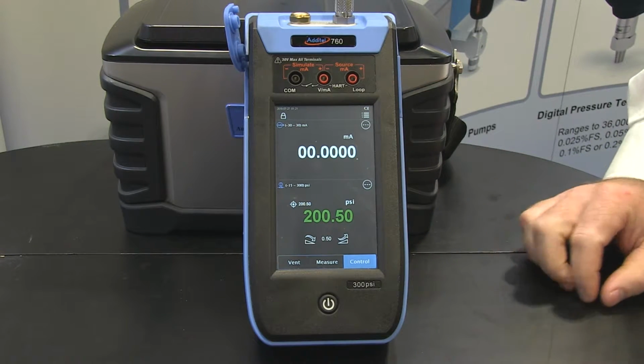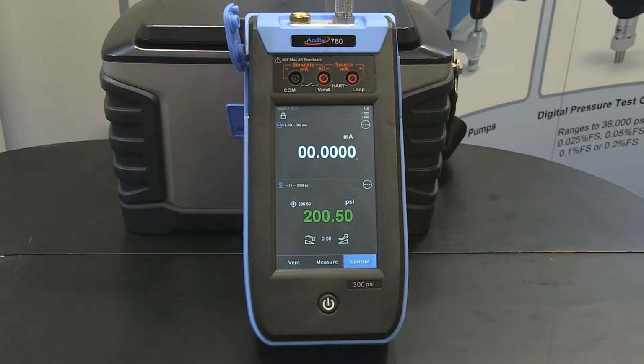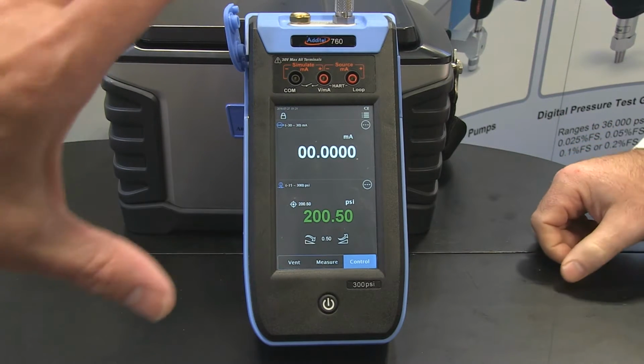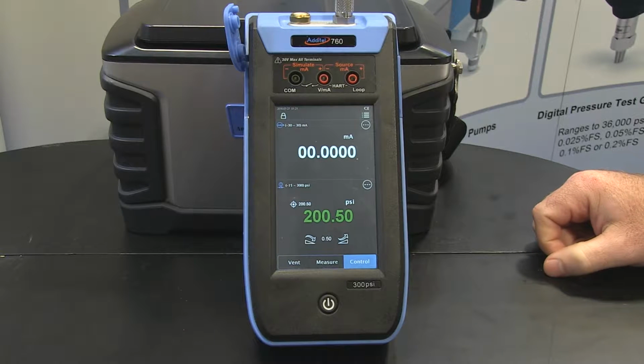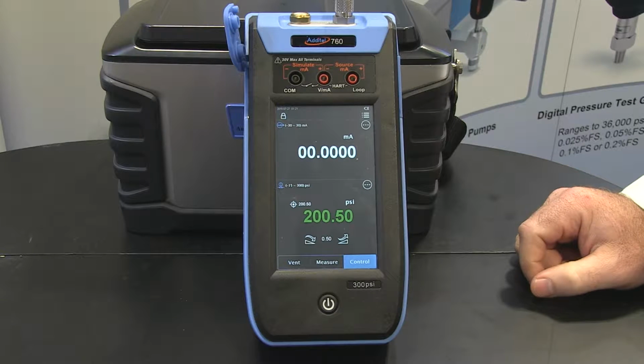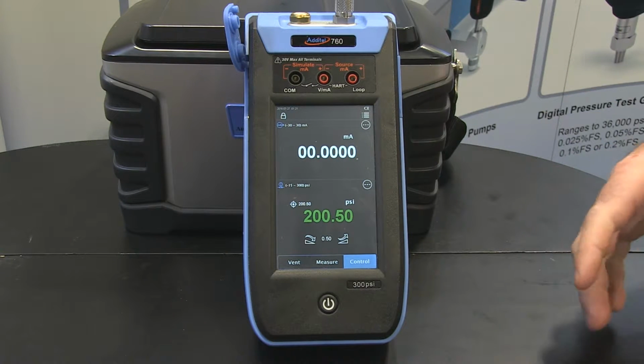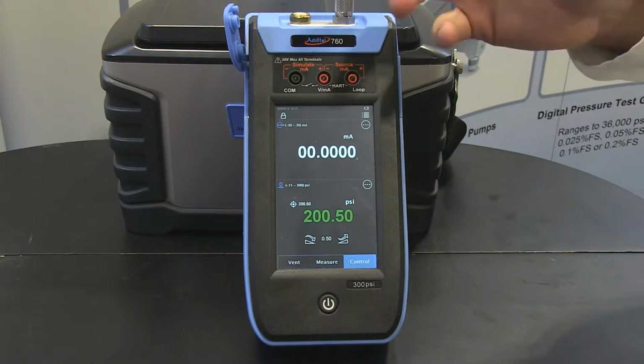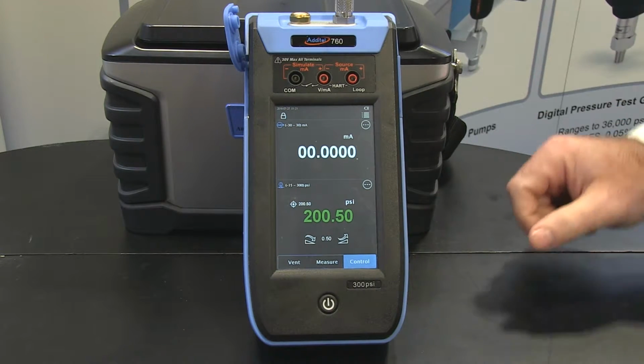So you could have a 300 PSI module built into the unit, and then you could plug in external modules in whatever range you buy, because you make modules within a certain range of each one of these base units. So if this is a 300 PSI, what's the lowest module that you can plug in? So I think on this one it's 10 PSI. Okay. So if you want better accuracy in lower parts of the range, you can do that either with external modules or internal modules. That's right. External, there's no limit. But it's not the control sensor in the external module. The internal is always going to be the control sensor.